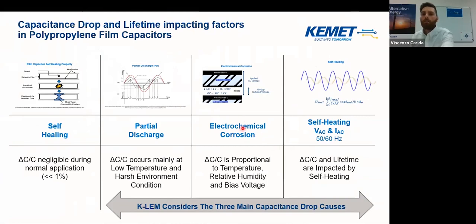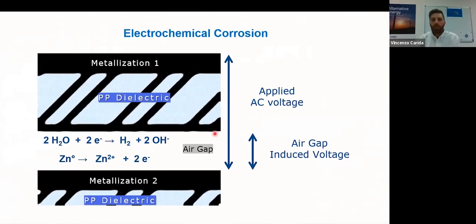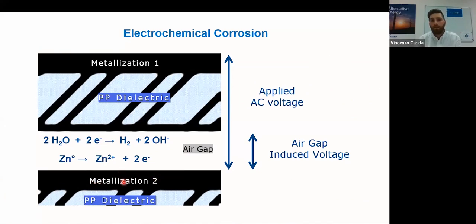The other capacitance drop mechanism is electrochemical corrosion. Electrochemical corrosion is due to the simultaneous presence of water and AC applied voltage. When water is present in capacitor windings, an electrochemical cell is formed, and with the voltage applied, the metallized layer could corrode in accordance with this reaction. This reaction rate is proportional to temperature, proportional to the AC voltage applied level, and also proportional to the relative humidity level.